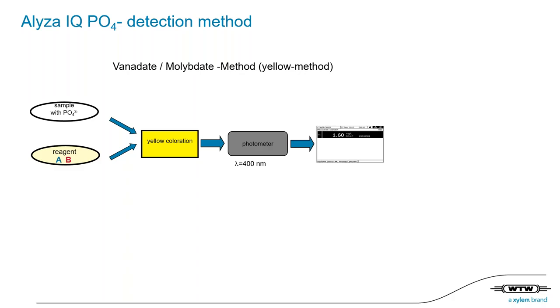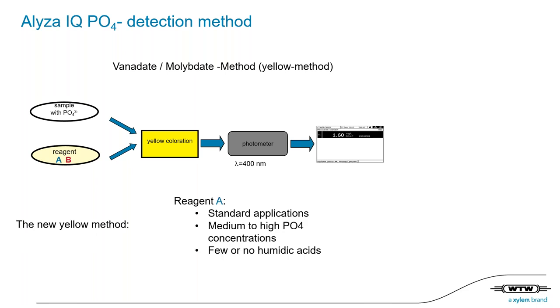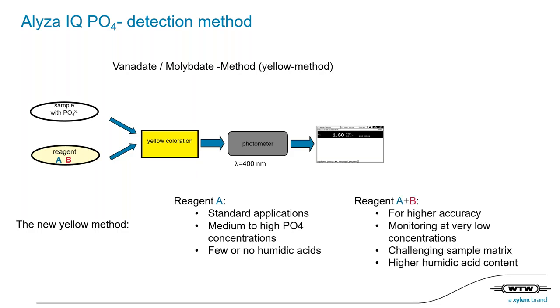Unlike with the P700, we improved the detection method for Alyza IQ, leading to the new yellow method. For standard applications, reagent A is used, which is comparable to the P700 IQ reagent solution. For low concentrations or challenging sample matrices, we now offer an additional reagent, the so-called reagent B, resulting in an even higher accuracy.